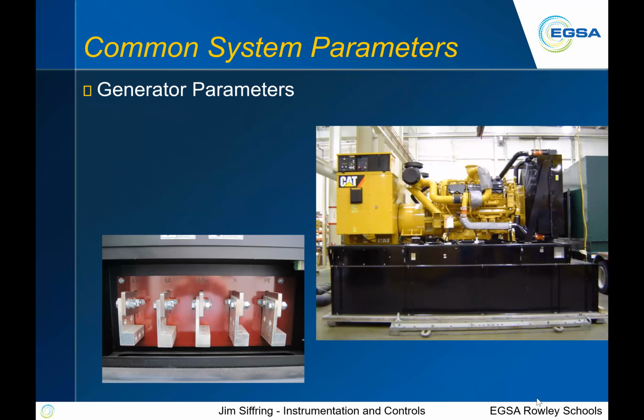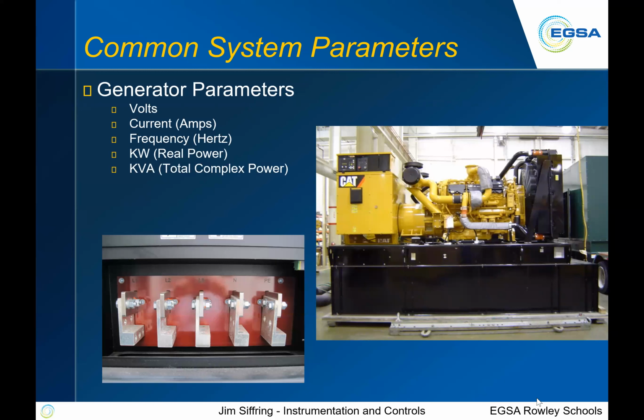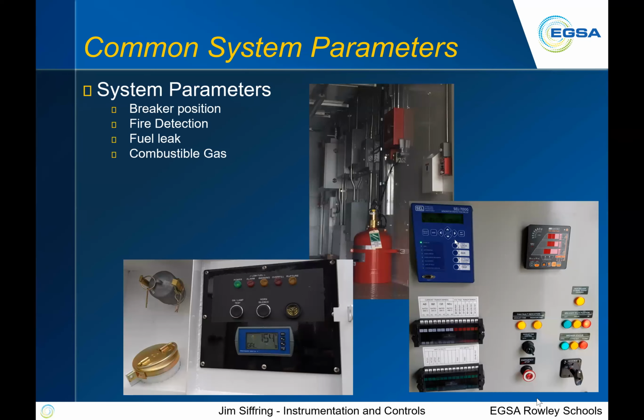And then we go on to the larger scale, to the genset itself, or what's coming out the back end of the generator, the electrical stuff. So volts and current in amps. We want to look at frequency in hertz. We want to look at kW, kVA, kVAR. We want to look at power factor, excitation voltages and currents, things such as that. These are all things that we want to keep an eye on. So, common system parameters, like other things that go along with the genset that may not be part of the genset.